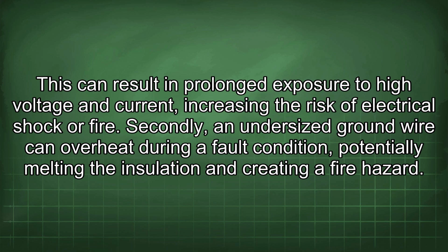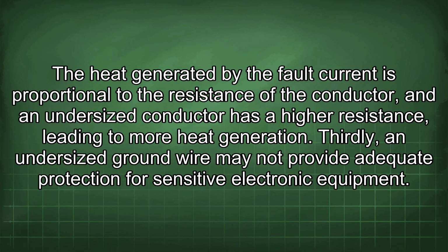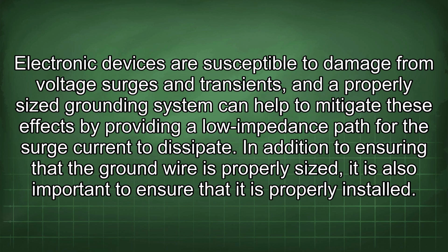Secondly, an undersized ground wire can overheat during a fault condition, potentially melting the insulation and creating a fire hazard. The heat generated by the fault current is proportional to the resistance of the conductor, and an undersized conductor has a higher resistance, leading to more heat generation. Thirdly, an undersized ground wire may not provide adequate protection for sensitive electronic equipment. Electronic devices are susceptible to damage from voltage surges and transients, and a properly sized grounding system can help to mitigate these effects by providing a lower impedance path for the surge current to dissipate.